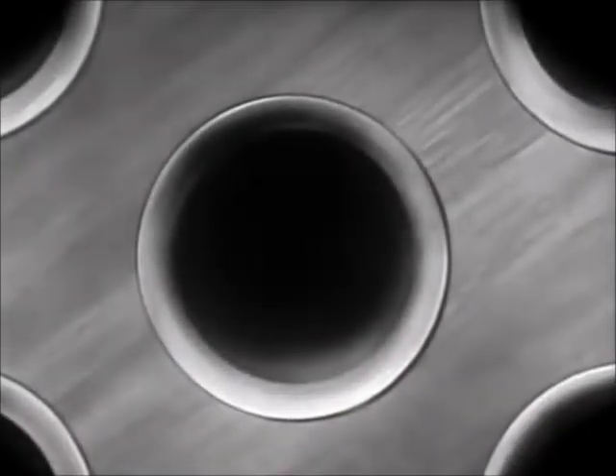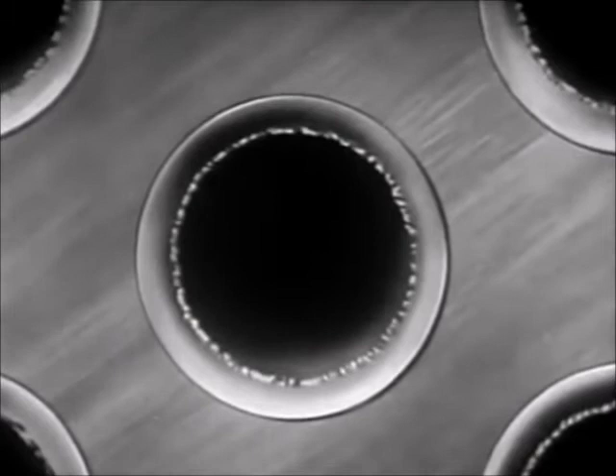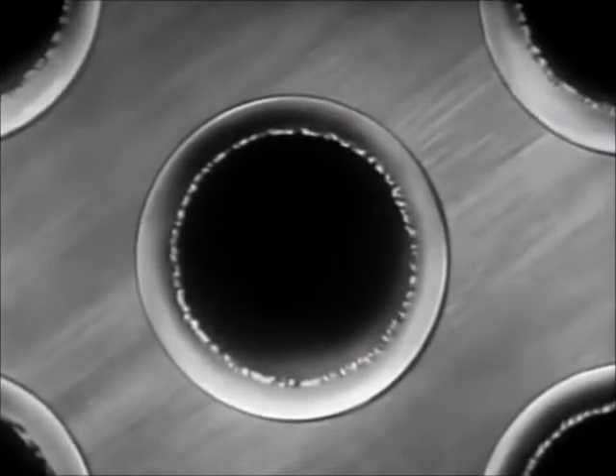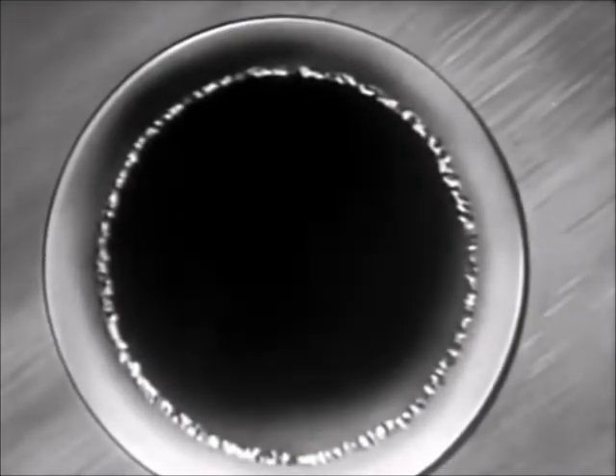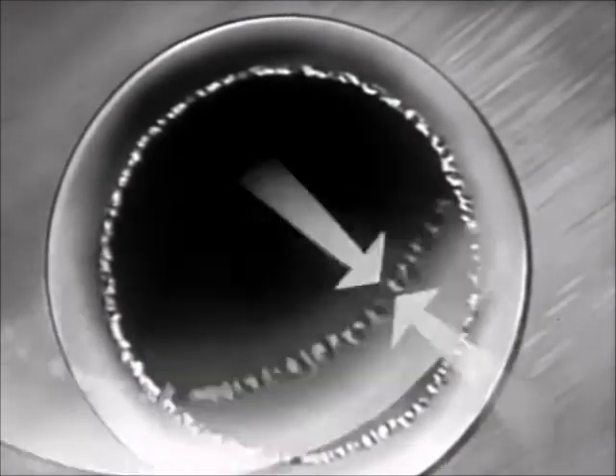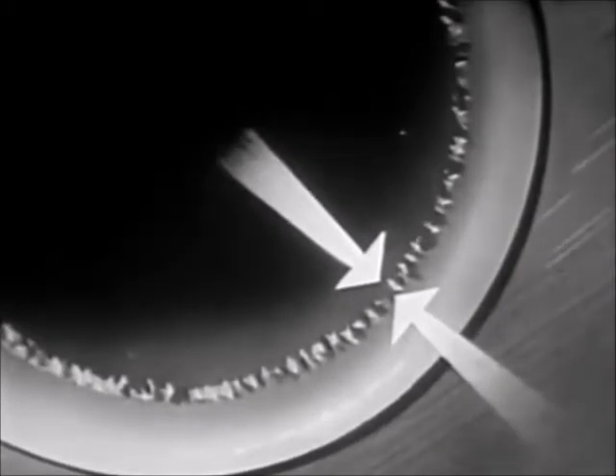So-called non-corrosive tubes actually do corrode when first exposed to seawater. This initial corrosive action forms a thin layer that protects the rest of the tube from corrosion. The protective layer is an extremely thin film. Don't confuse it with dirt and scale, which must be removed. In the cleaning process, if the protective layer is gouged or scratched, corrosion attacks the exposed metal, causing a weak spot. So be careful. Don't use wire brushes, metal slugs, nor anything that can damage this thin protective lining.